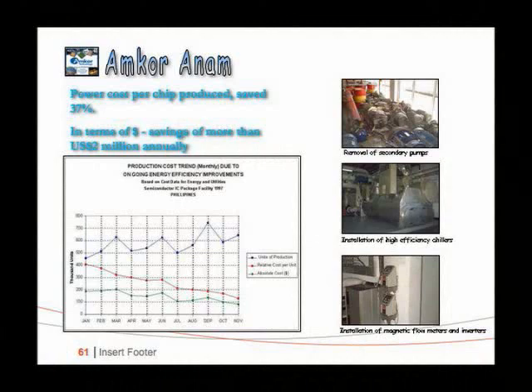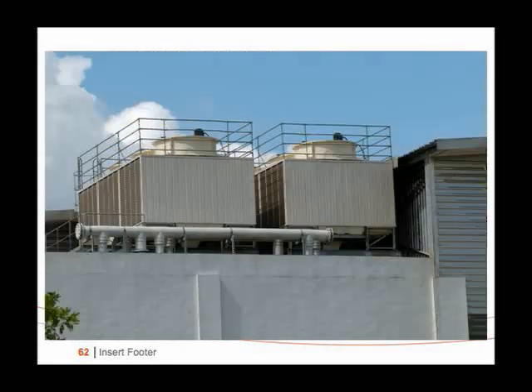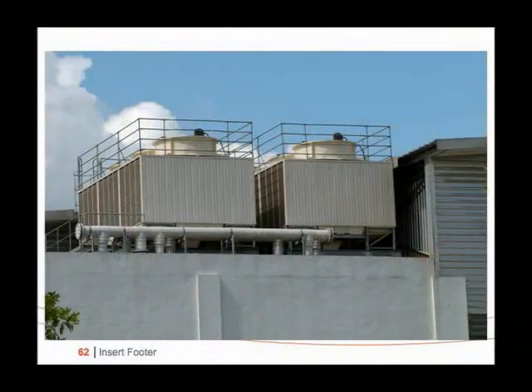This is a bunch of secondary pumps we took out from another project. And finally, the fifth loop of the HVAC system is cooling towers. We need to dump the heat we've collected in the building, but we need to give the cooling towers room to breathe. They need a very large amount of free area for air to go in and then get discharged. You put it like this, and this fellow will come back here, and this guy will come back here. It's good to see old friends, but not when they are hot and wet.